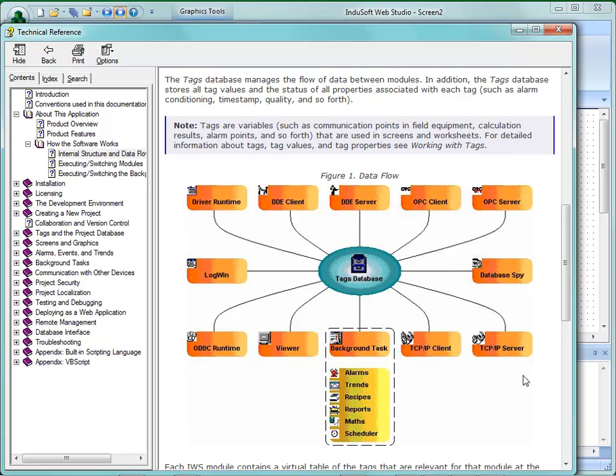Under the TCP/IP server are the screens. As you're viewing screens and changing values or set points — say on a slider or entering a number — it goes into the tag database. From there it may go out to the driver runtime and to the PLC. If a temperature, level, or pressure updates, the driver runtime reads the real-world values, updates the tag database, and then the screen updates after that.